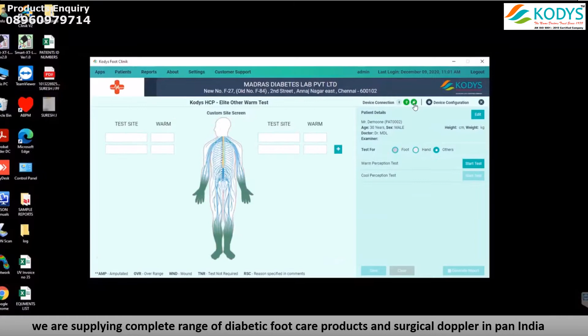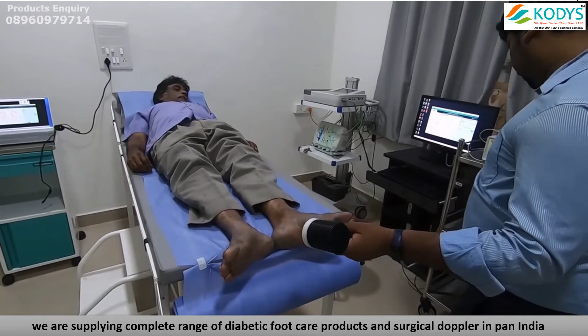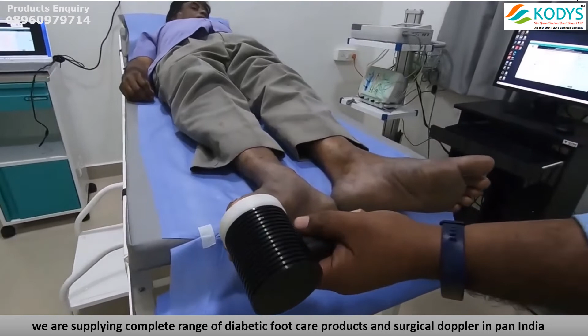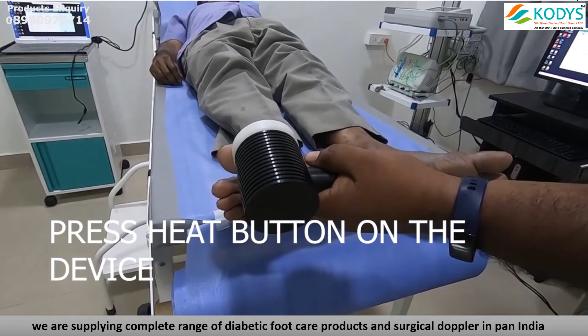After clicking start test, now it is on the warm perception test. Here you can note the temperature will rise to 32 and it will give you a beep stating that the machine is ready to start the testing. Now we have to place it on the foot of the patient, the right great toe. So this sensor should touch the right great toe and we have to press this button. Then the temperature will rise in a slow manner as the program is in slow mode.